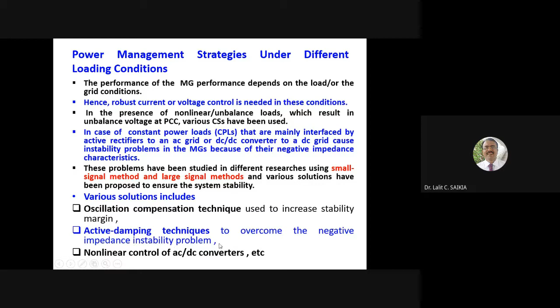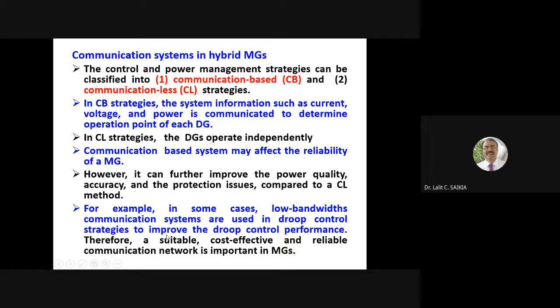Various solutions include oscillation compensation techniques used to increase the stability margin, active damping techniques to overcome the negative impedance stability problem, nonlinear control of the AC/DC converters, etc. There is also a communication system in the microgrid. The control and power management strategy can be classified as communication based and communication less, CB and CL. In CB, system information such as current, voltage and power is communicated to determine the operating point of each DG. In CL, DGs operate independently. A communication-based system may affect the reliability of the microgrid. However, it can further improve the power quality, accuracy and protection compared to the CL method.